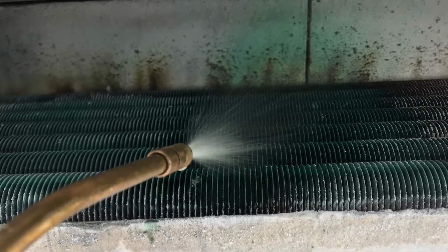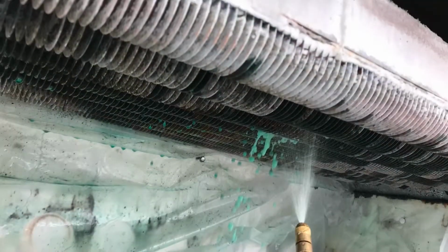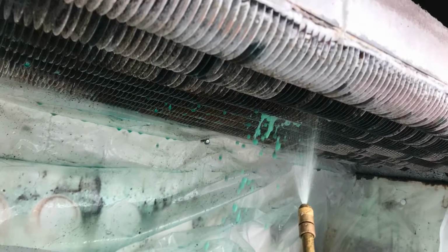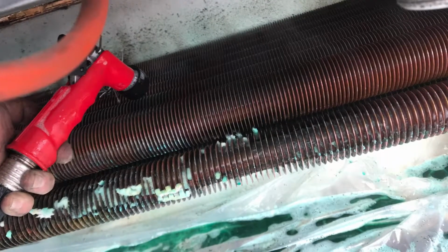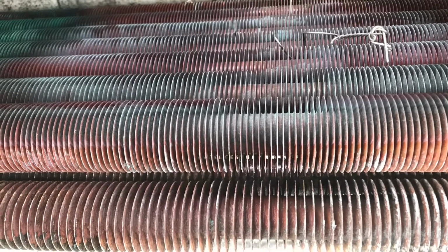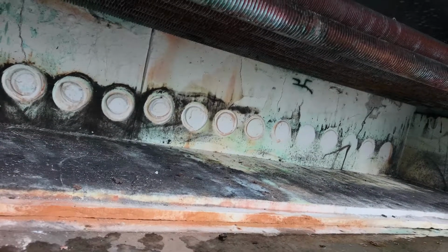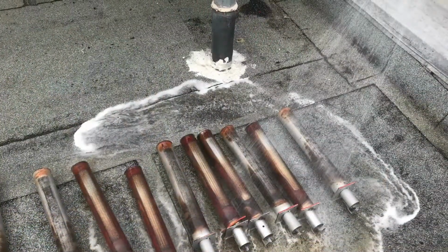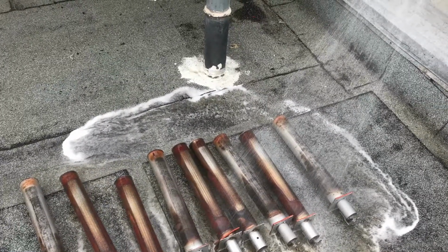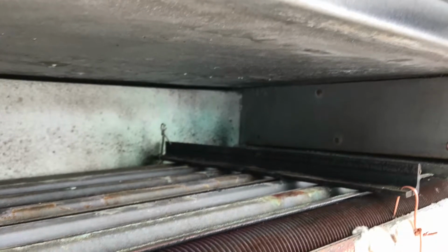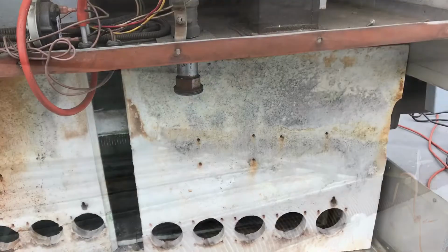And you're going to line the cabinet in plastic. Coat the heat exchanger with Evap Power or Simple Green. And actually wash with a hose. Careful not to saturate. And here is a nice clean heat exchanger. So once that's all finished, remove your plastic. While your burners are out, go ahead and wash your burners, inspect them, and basically just put the unit back the same way you took it apart.